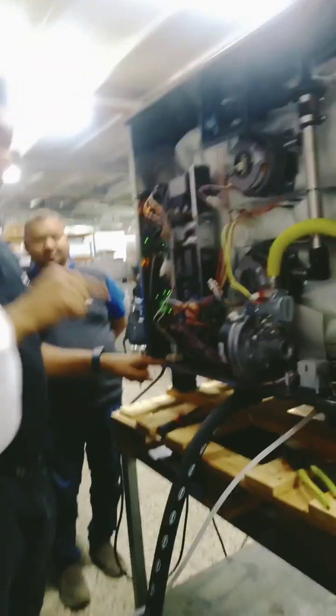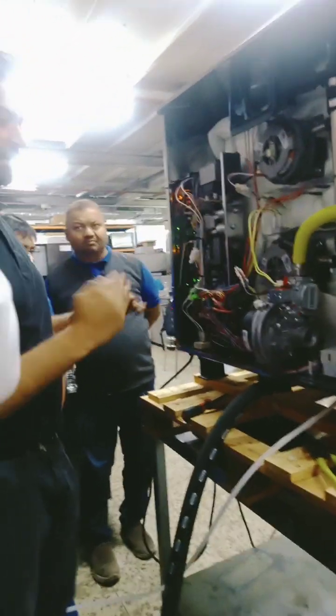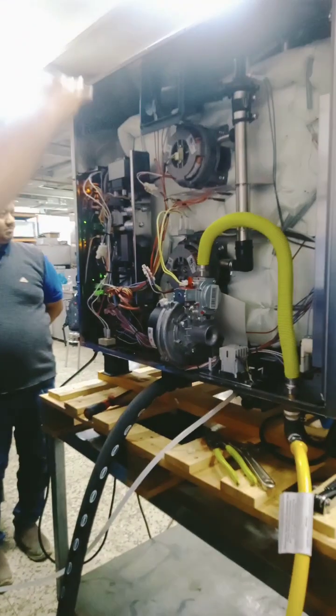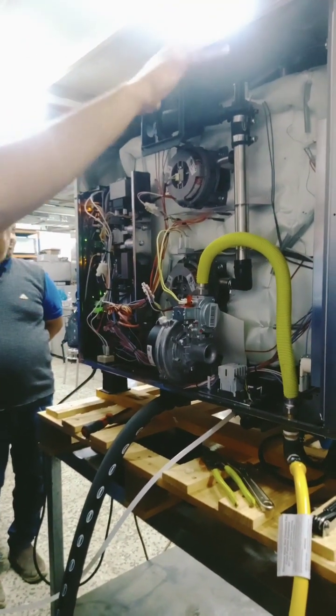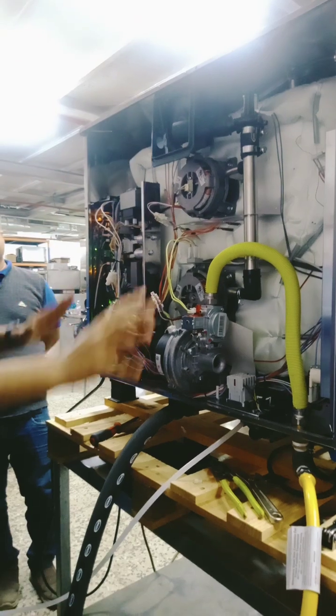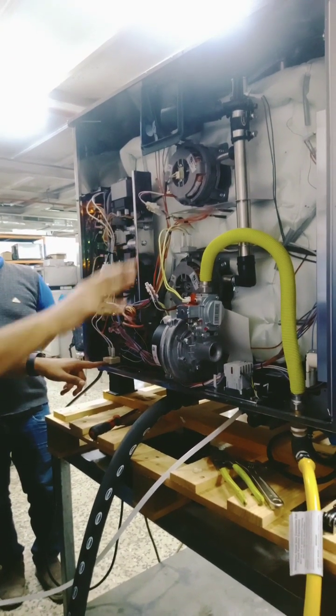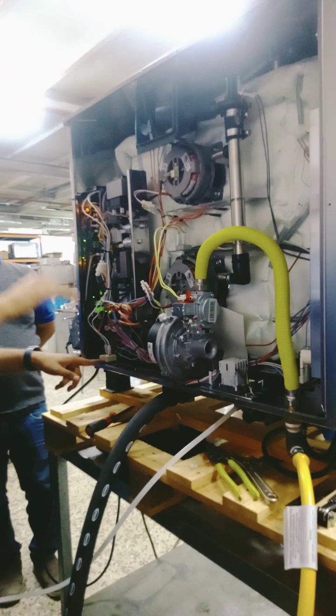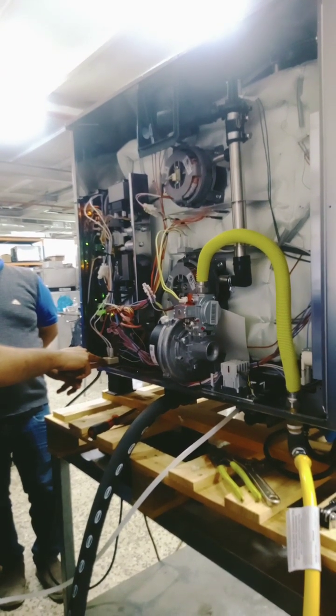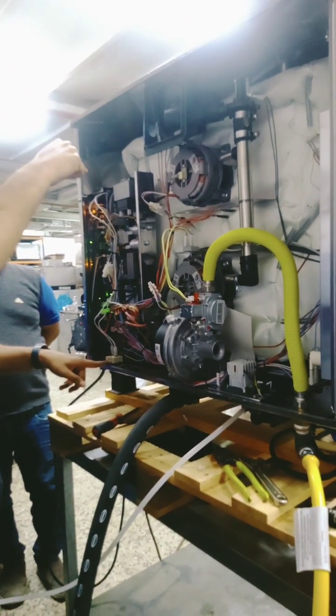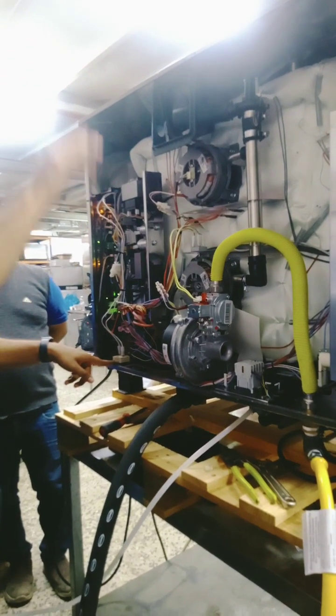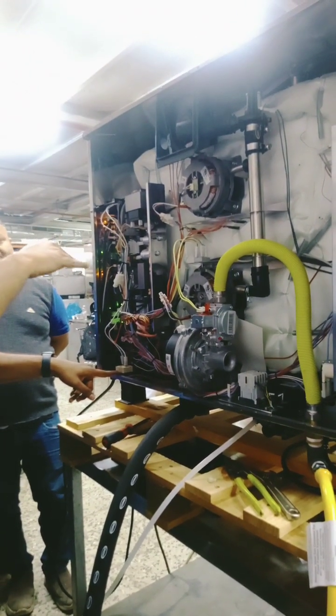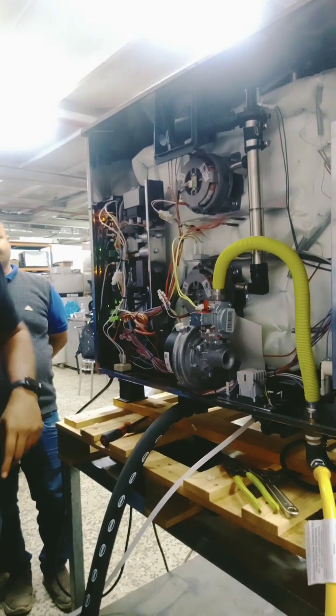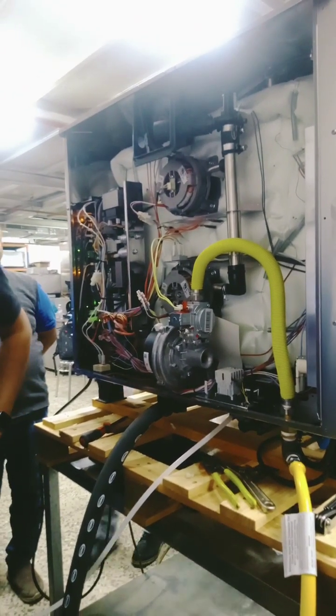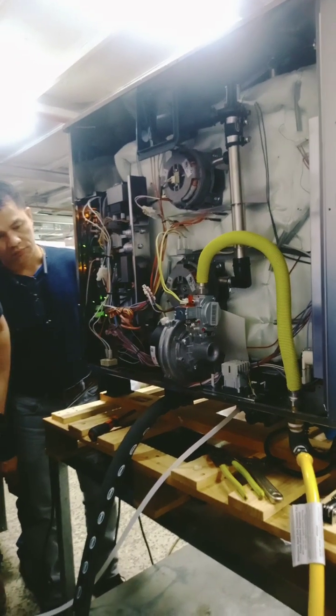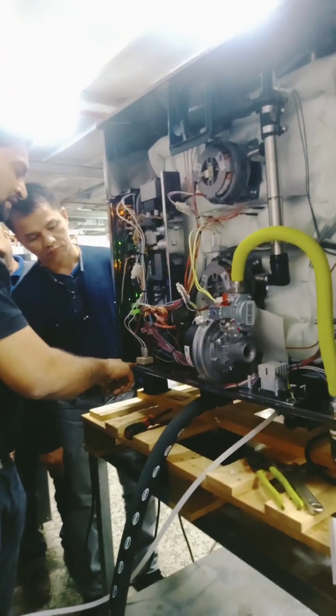If this body is increasing in temperature due to some reason, maybe there is some hot and cold switching here, or there is no ventilation here, or the cooling fan is not working, then this area gets hot. The body temperature and every component keep increasing slowly. This helps it trigger at a lower temperature. So when this temperature increases, the probe trip temperature will decrease. Ambient temperature? No, it's cold. Okay, so this is the one.